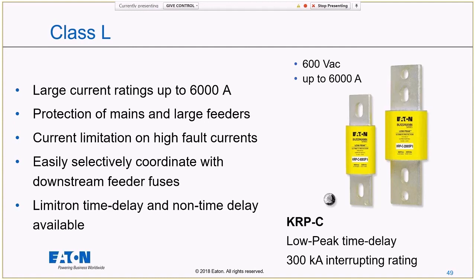And then again, of course, anytime where we need more than 600 amps, we have to go to the Class L fuse. These are really the only fuses that go up to those really, really high amp ratings.